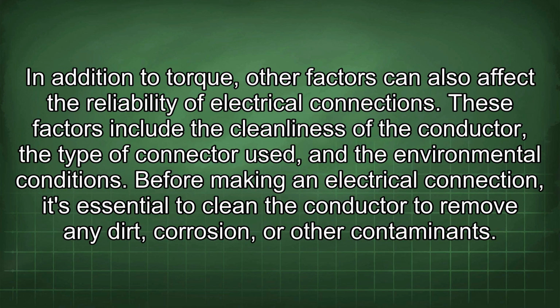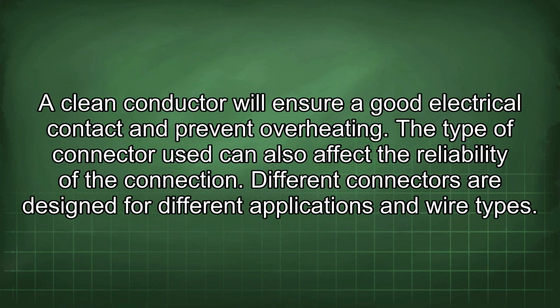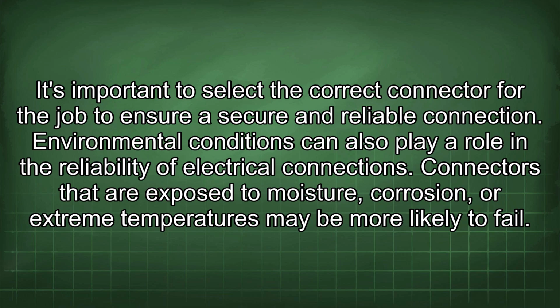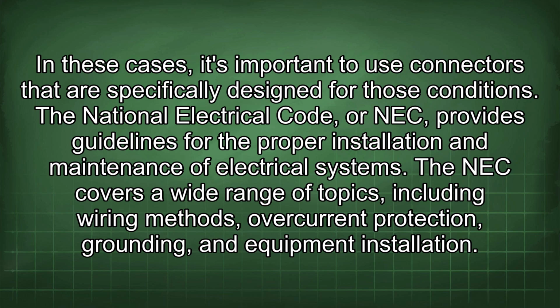In addition to torque, other factors can also affect the reliability of electrical connections. These factors include the cleanliness of the conductor, the type of connector used, and the environmental conditions. Before making an electrical connection, it's essential to clean the conductor to remove any dirt, corrosion, or other contaminants. A clean conductor will ensure a good electrical contact and prevent overheating. The type of connector used can also affect the reliability of the connection. Different connectors are designed for different applications and wire types. It's important to select the correct connector for the job to ensure a secure and reliable connection. Environmental conditions can also play a role in the reliability of electrical connections. Connectors that are exposed to moisture, corrosion, or extreme temperatures may be more likely to fail. In these cases, it's important to use connectors that are specifically designed for those conditions.